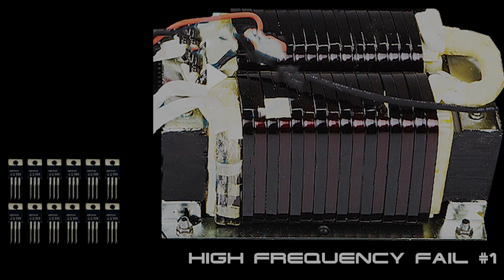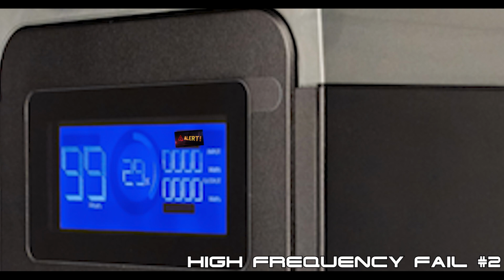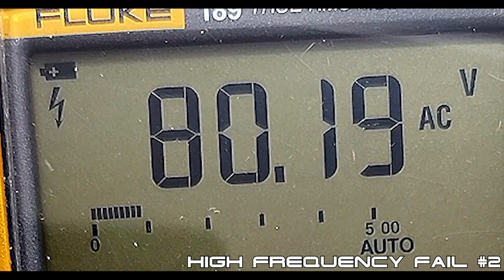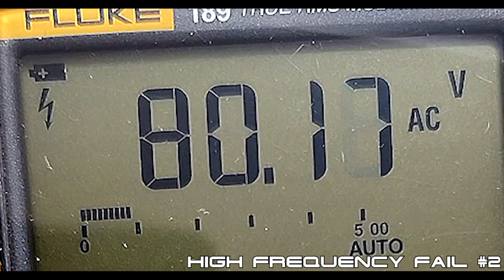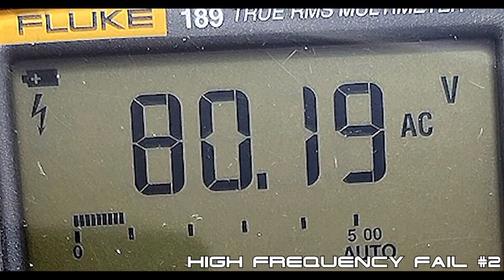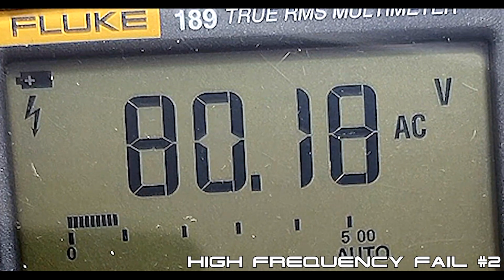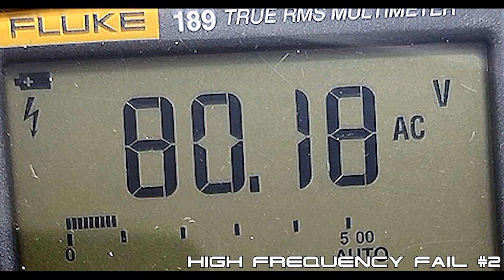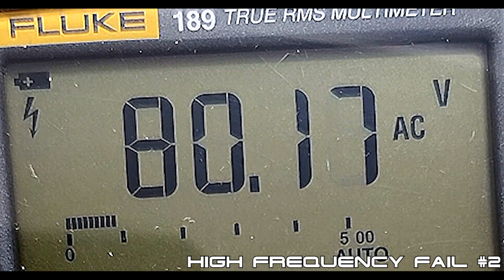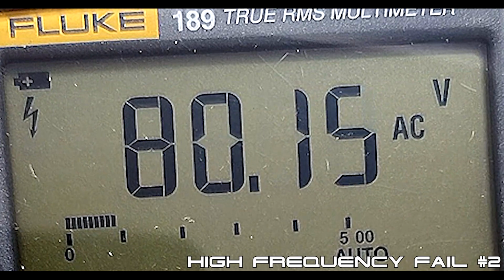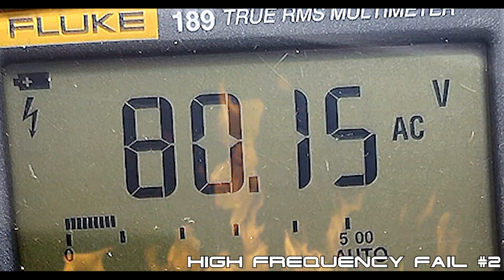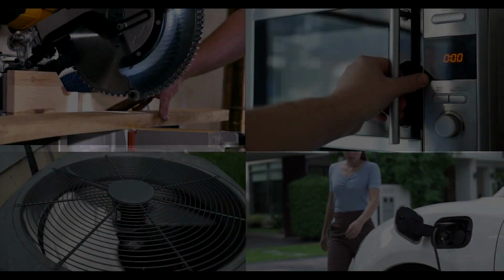Another major issue with many of these high-frequency solar generators and inverters is their overload protection. Rather than shutting down the inverter's output during an overload, most will lower their output voltage to as low as 80 volts AC and then slowly ramp it back up, effectively creating a brownout. The problem is that in order to maintain the load's power draw, the load causes an increase in current, which can damage the windings of electric motors and the insulation of wiring in your appliances, eventually leading to short-circuit-induced fires.